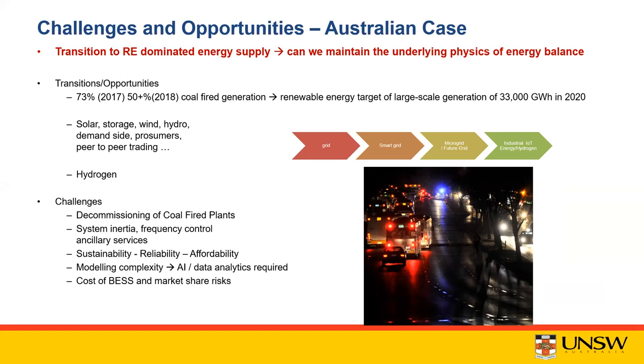One of the issues identified for this blackout was that there were many rooftop PV installations. So to the system operator, the total demand is not actually the total demand before the accident happens - it's total demand minus rooftop PV generation. However, when the disturbance happened, the inverter protection was activated, so suddenly the total demand seen by the system operator increased instead of decreased, for what otherwise should be supplied locally by distributed PV generation. So this is one of the reasons why the control didn't work, causing a major blackout in that state.